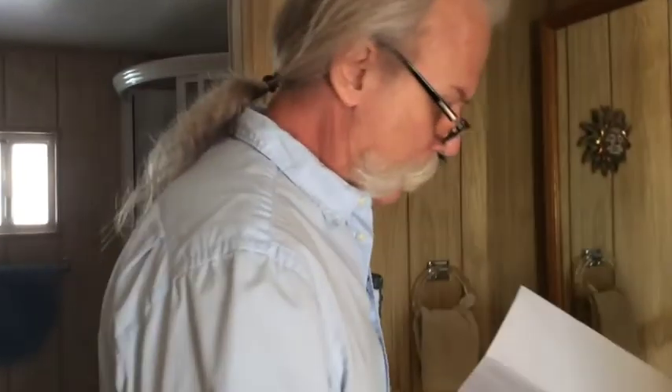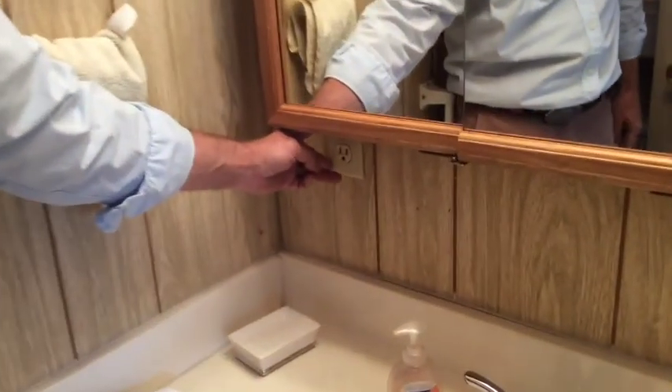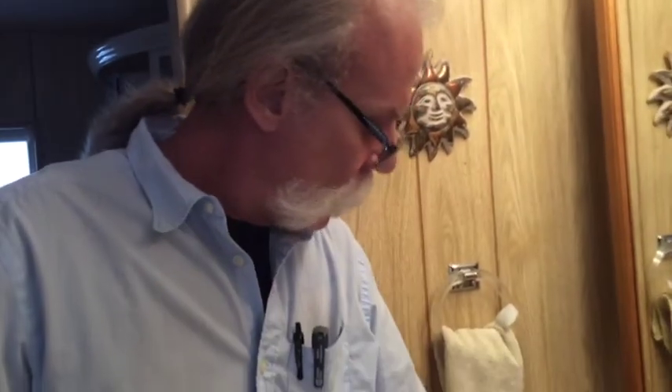Now in the bathroom — just one bathroom in the house. The outlet here is not ground fault circuit interrupted, which is the way the house came, so we don't consider it improper — but it's easily added by putting in a new outlet to greatly upgrade your safety. Looking under the sink, they've re-piped with copper here. So the bathroom's been re-piped with copper, no leaks, everything looks good and fairly redone. There's no light in the shower area except for the heat lamp.